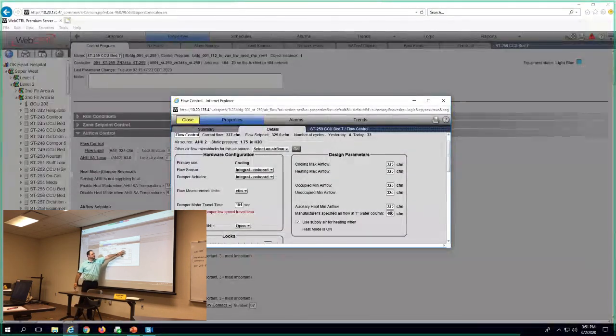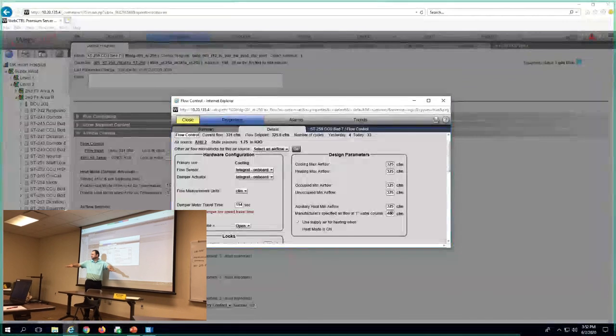Now these other airflows, I hope you don't ever have to mess with them either, but you can change them. Once we get everything all done, tuned, tied in, the test and balance finished, it should be at what TME designed it at. But if you have to increase the max cooling CFM, you can do it right here. Max heating CFM, you can do it right here.